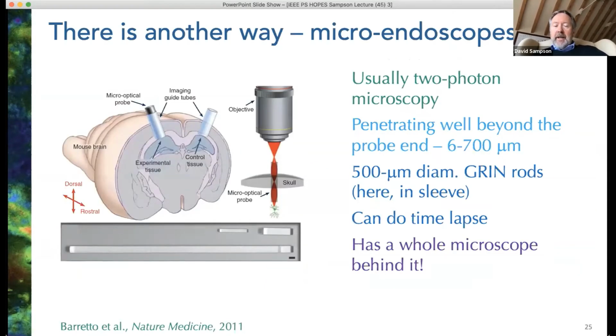But there is another way, and that is through the microendoscope. Usually multi-photon microscopy, but not exclusively. You can see what it consists of here. Essentially, we take a GRIN lens of the type shown here. They can be multi-element or single element. This one here is about 500 micrometers in diameter. You can put it into the object, and at the bottom of that, at some depth, you can capture that image. You can penetrate with multi-photon microscopy well beyond the end of the probe, possibly to 600 or 700 microns, possibly even further at the very edges of the capability.